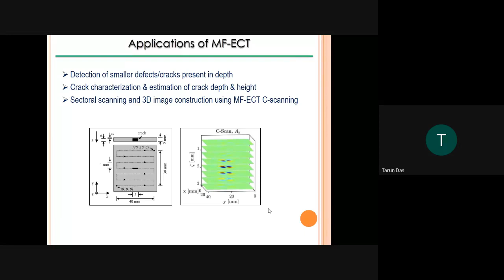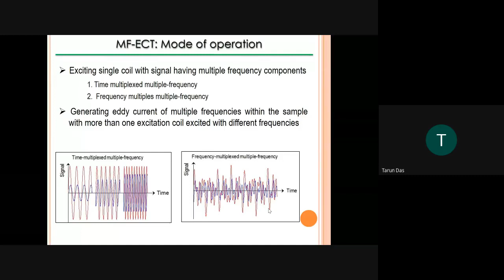Multi-frequency eddy current can operate in various ways depending upon the requirements. One can excite a single coil with a signal having multi-frequency components, either in time multiplex mode or frequency multiplex mode. Another mode pertains to generating eddy currents of multiple frequencies in the sample with more than one excitation coil excited with different frequencies. Here we can see two modes, that is, one is time multiplex multiple frequency and the other is frequency multiplex multiple frequency.